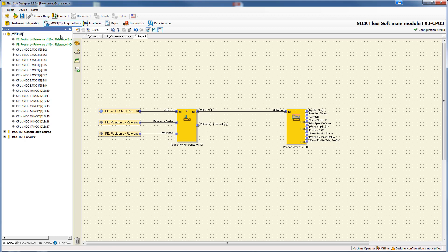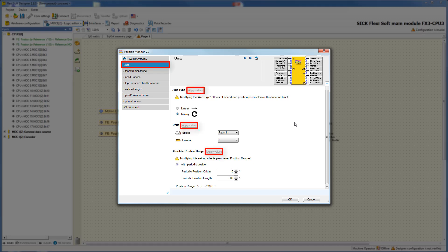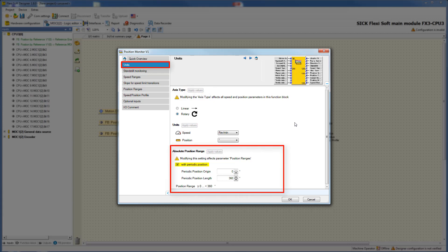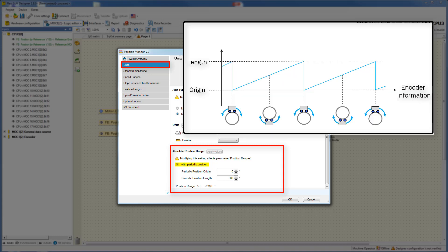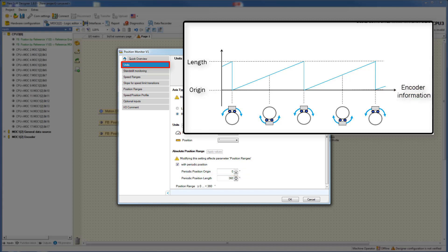Let's turn to the configuration menu to configure the function safely limited position. First you have to apply the values from the previous function block. For the settings of the absolute position range, the periodic position window can be activated. This function is used for applications where the mechanical position is periodic, like a mechanical press, where the beginning and end of the position range adjoin each other — meaning the mechanical position repeats every 360 degrees. On the horizontal axis there is the encoder information, where you can configure the origin as well as the length of the periodic position. For a mechanical press, the length of the periodic position is 360 degrees.